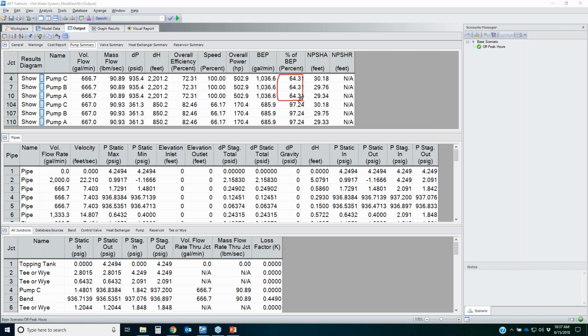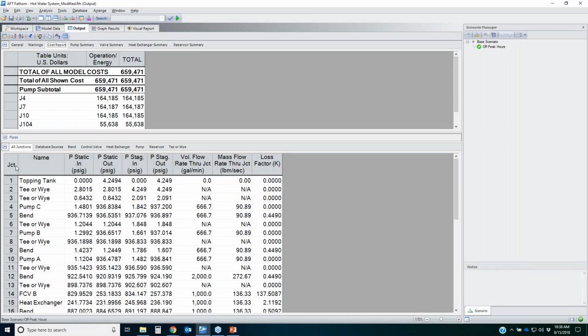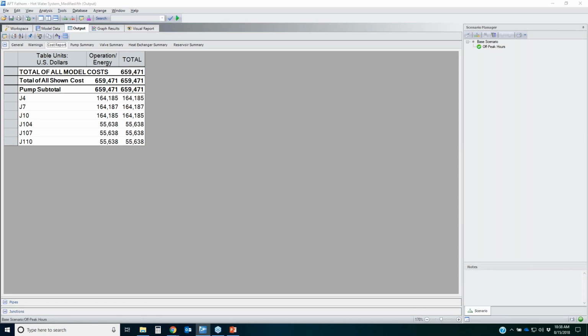If you incorporate a variable speed drive, look at this. If you drop the speed by about 34%, you can still be operating at 97% of your best efficiency point. So this is where you're going to experience the energy cost savings. So if I go to my cost report tab, you'll see the total costs of both individual systems. So with control valves, you're looking at $165,000 a year for each pump versus with a variable speed drive, $56,000 for each pump.